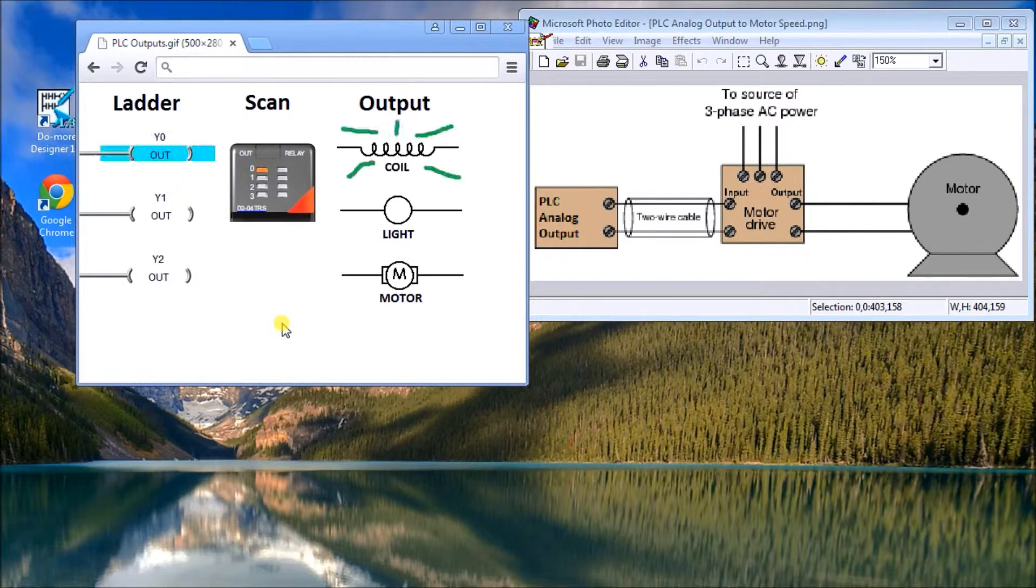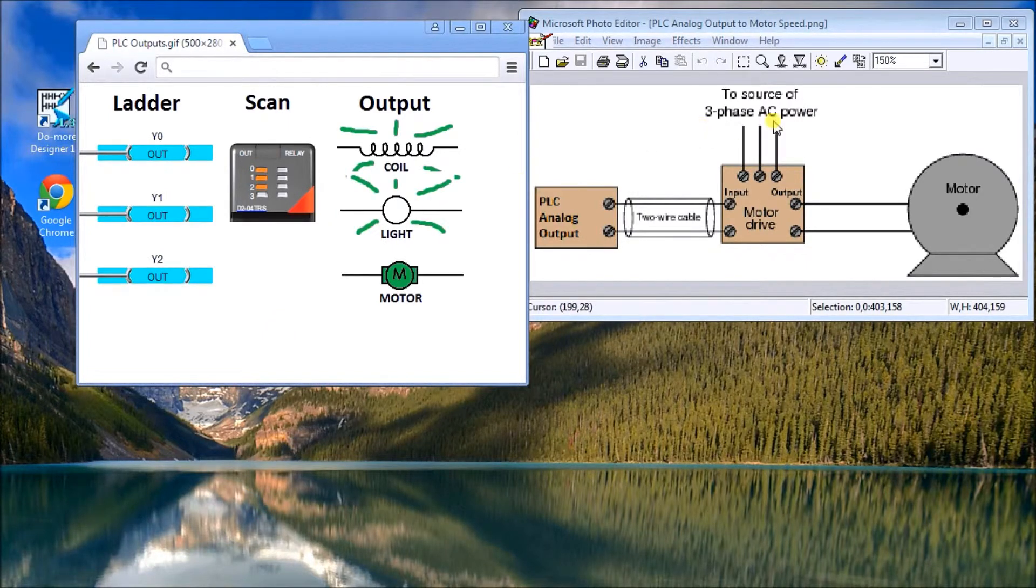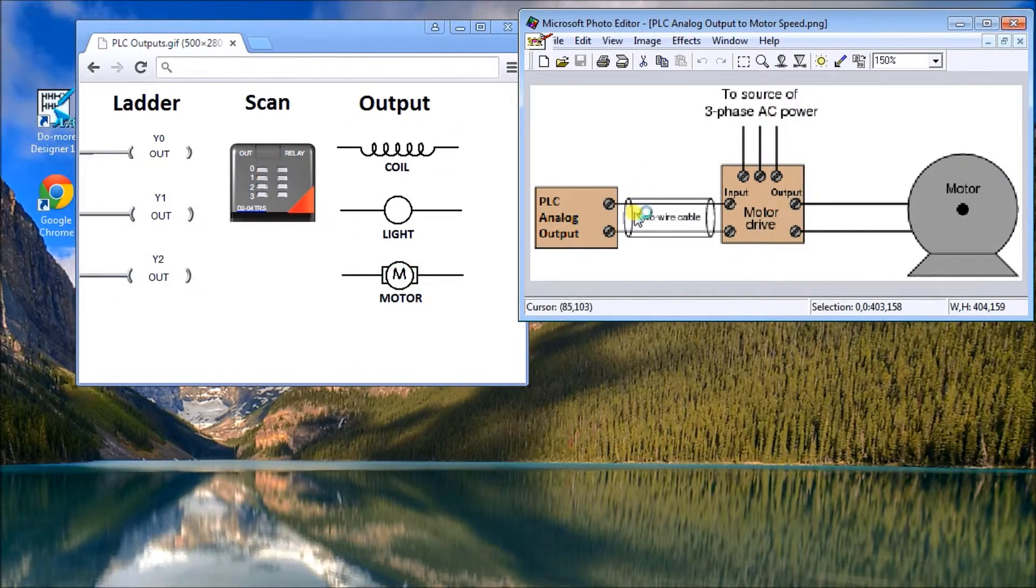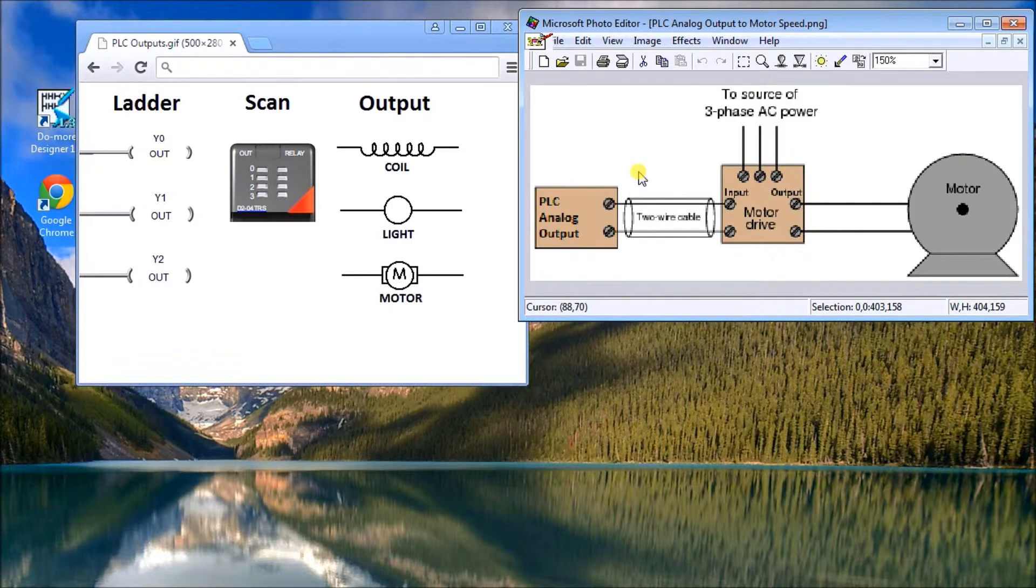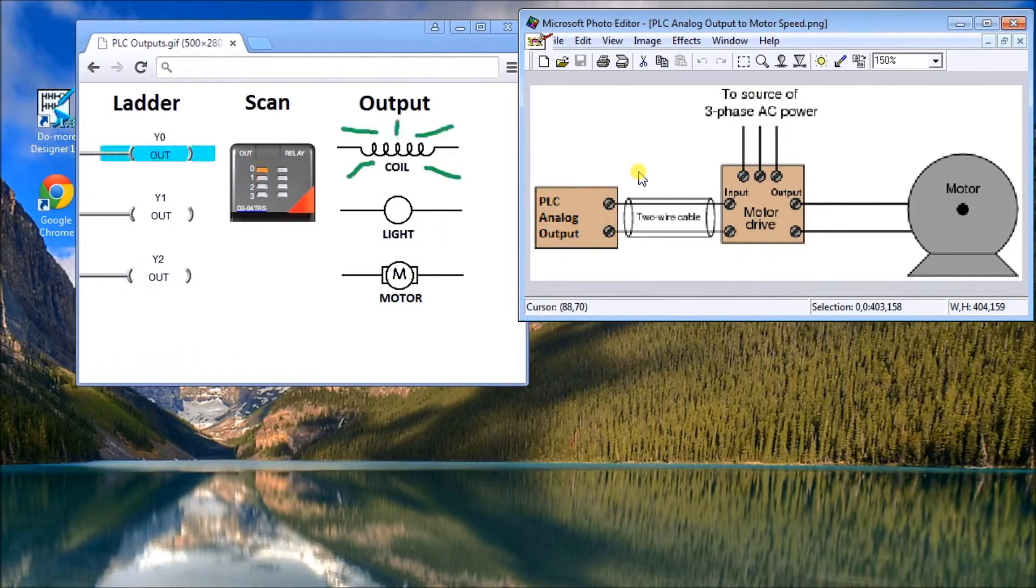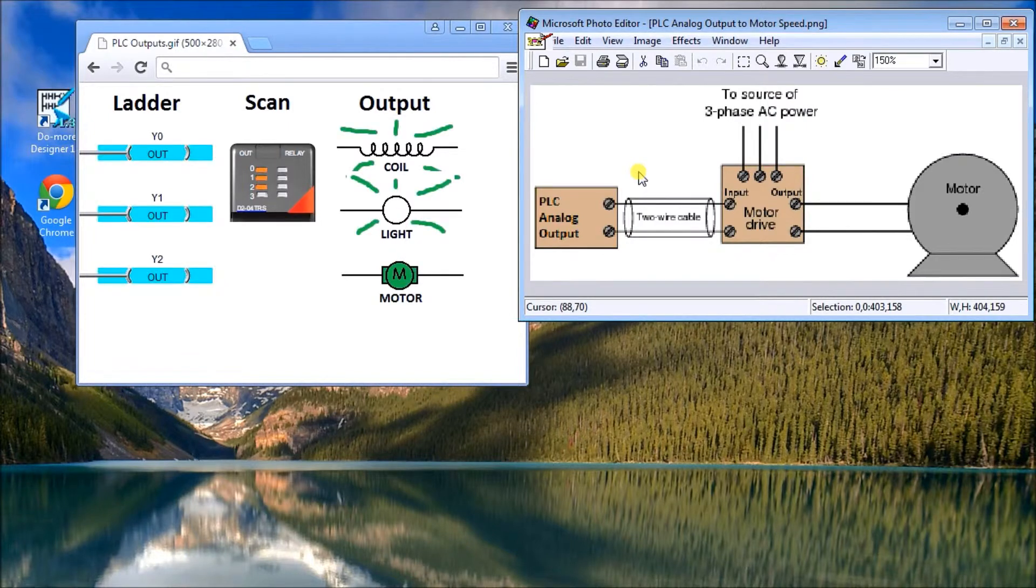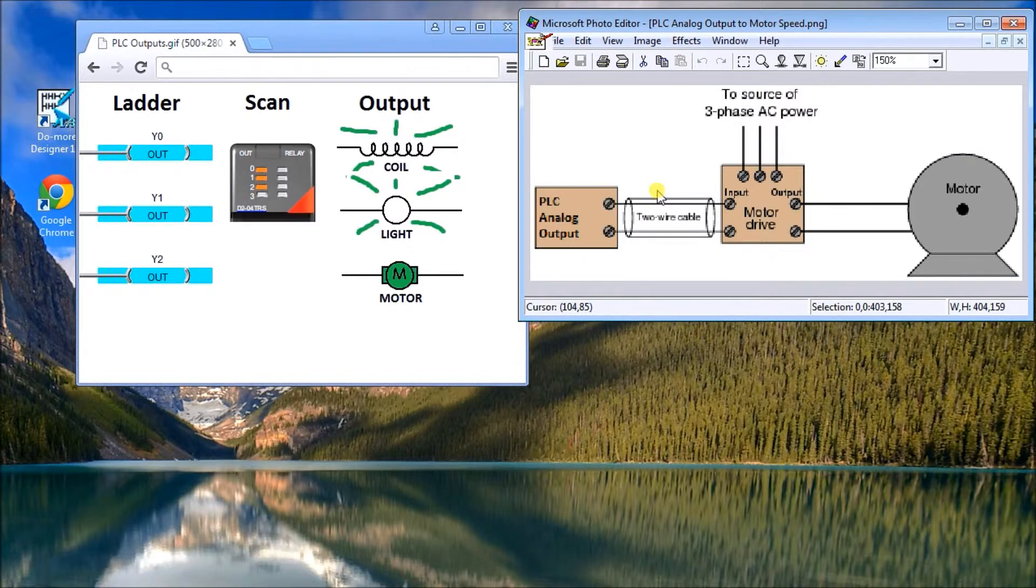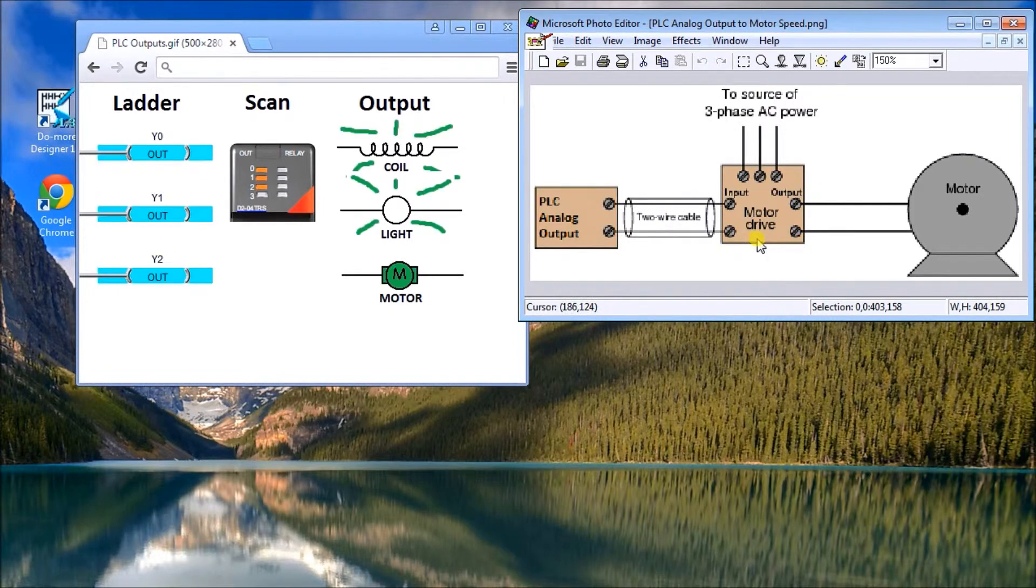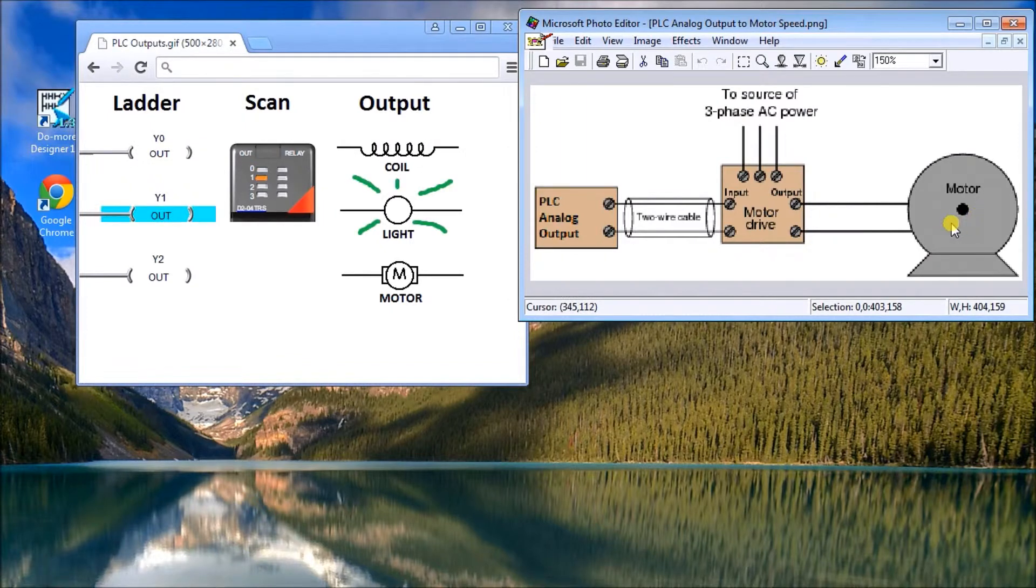The other form of output would actually be analog. In analog, you actually output a series or a range of values. Typically, an 8-bit resolution would be 256, so your values would go from 0 to 256. That would then be translated to a 4 to 20 milliamp or a 0 to 10 volt. That goes into, in our particular case here, a motor drive, and that will actually turn the speed of the motor the appropriate amount.